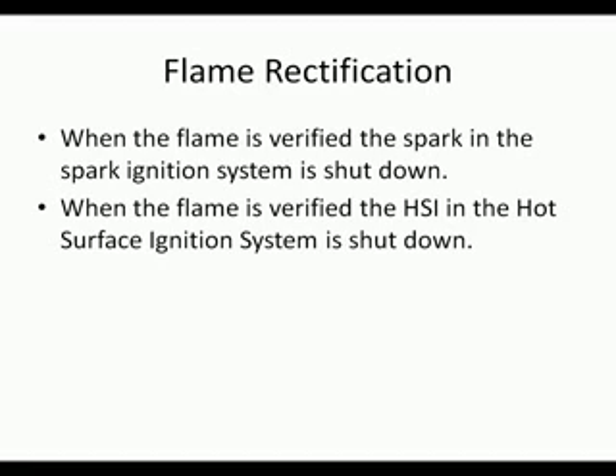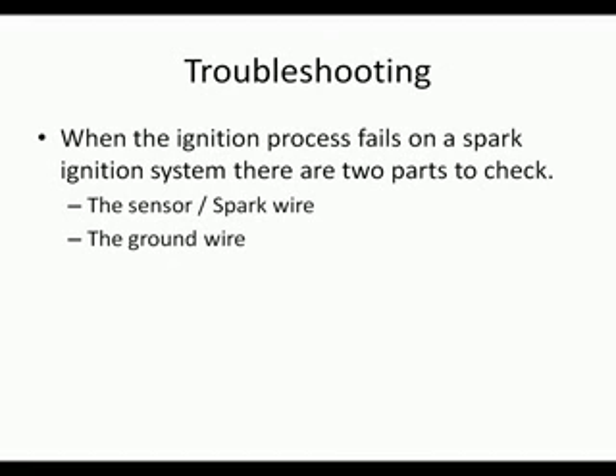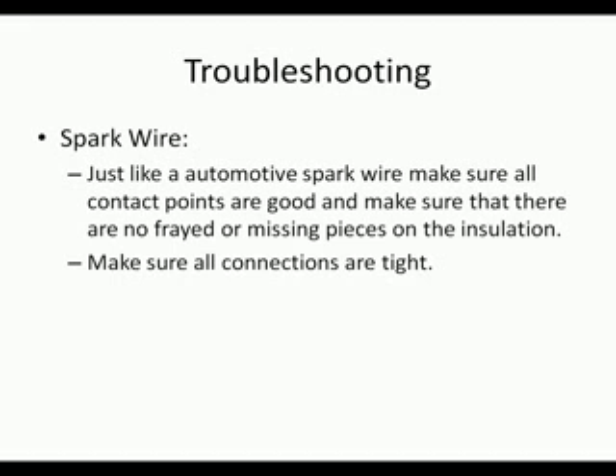When the pilot flame is verified, the main burner is allowed to open. If the flame goes out, the DC current stops flowing to ground. The control senses the stop of current flow and closes the main burner. When the flame is verified, the spark ignition system is shut down. When the flame is verified in the HSI, the hot surface igniter is allowed to cool.